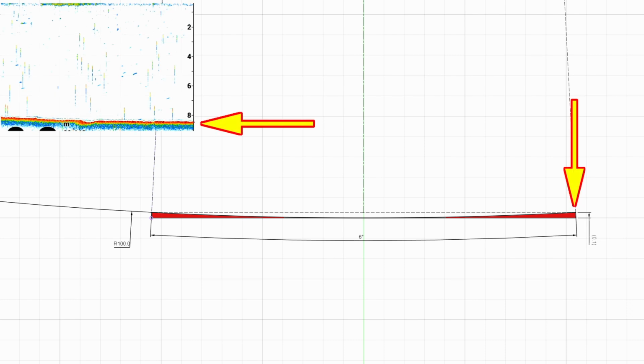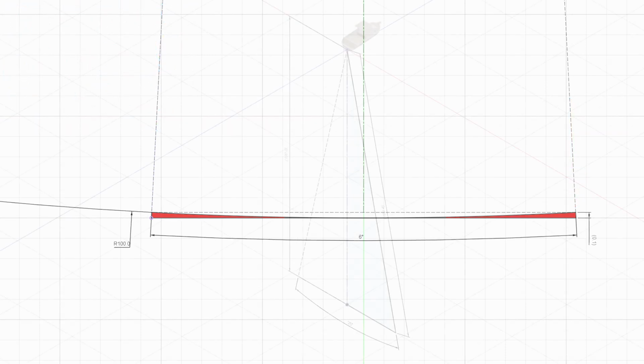This slide shows the shadow area of the 6-degree beam at 100 metres depth. What happens with this is that any fish within that shadow area, which is 0.1 metres or about 4 inches deep, cannot be detected. The shadow area for that narrow beam is really quite negligible on a flat seafloor.